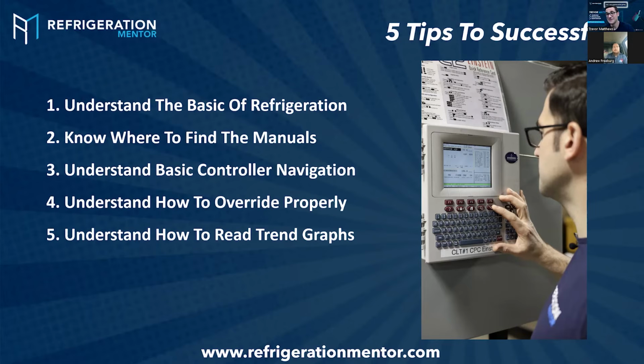Yeah, but sometimes it's so necessary to save you. And that's why I put it in there properly, because it's so important to understand it. I've done it multiple times, put something into manual defrost to help out before going to defrost the case and trying to get it started. But if you put it in override and leave it in override, then forget to take it out, and then you leave the store and they go unload the case, they'll be calling you back because the case isn't pulling down. What is going on here?